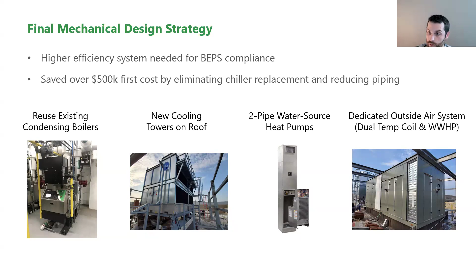So at that point, the main hurdle for GW was maintenance concerns, like I've mentioned, because the downside of having distributed compressors would be if one of those fails, they're not easily accessible to maintenance staff without disrupting students in their dorm spaces. So that is something that we discussed with them. But at the end of the day, the energy modeling that we were showing them was showing that the ECMs alone weren't going to bring Thurston Hall into BEPS compliance. So that's ultimately what convinced GW and their maintenance staff that going towards the water source heat pump system was the best path going forward.